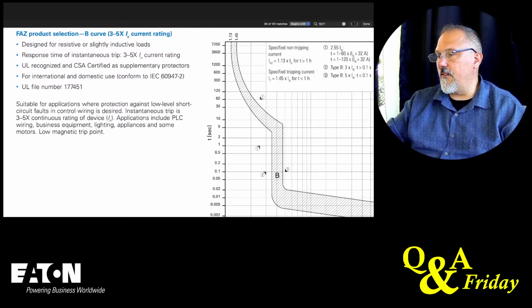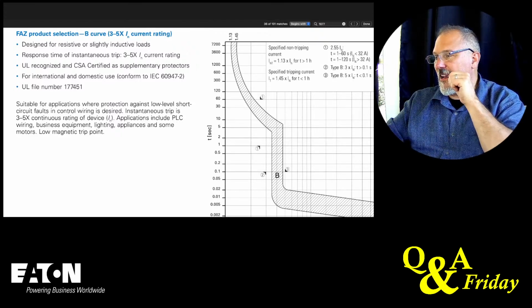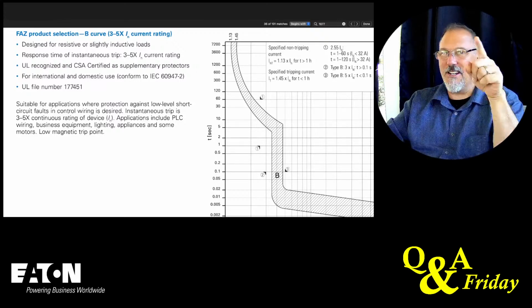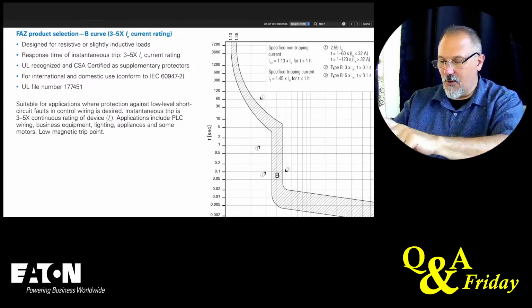Yep, when performing arc flash studies on an MCC, I always consider that the main breaker is not isolated. It gives me more, okay. Is that a correct assumption? Given how most MCC main breaker sections are constructed, are there MCCs that provide full isolation? We're going to get to that question. That's not quite on this one.